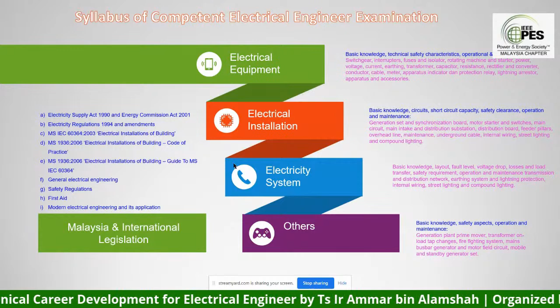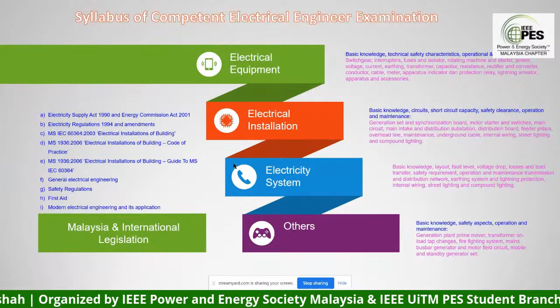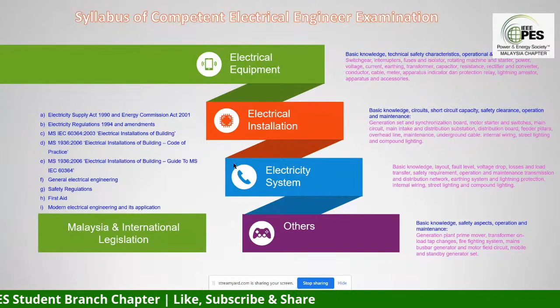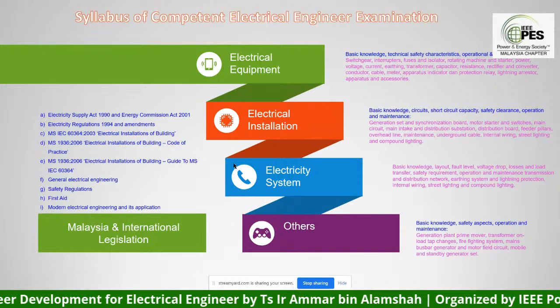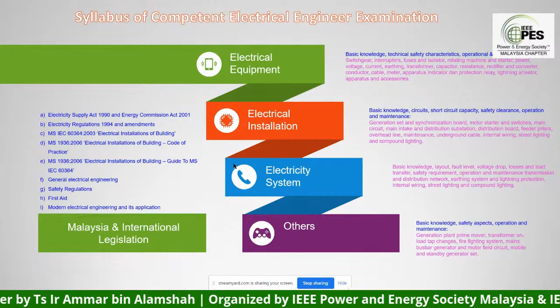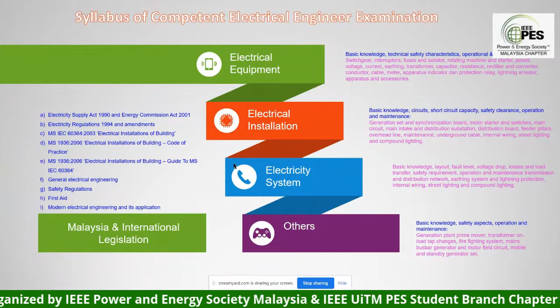What do you mean by operational and maintenance? It refers to the operational of circuit breakers. This circuit breaker rated 11 kV needs a special way to handle it. You must wear protective gear, we call it an arc flash suit, to do switching and to rack in and rack out of the breaker, because during the rack in and rack out of the breaker, there is a potential of arc flash happening in case of failure of the component of the breaker.